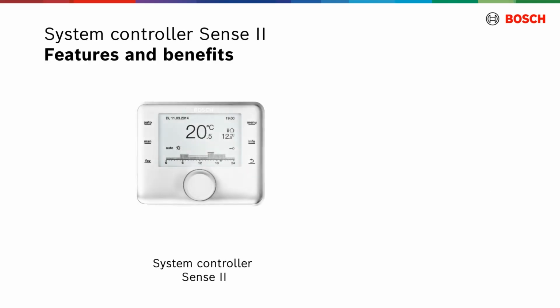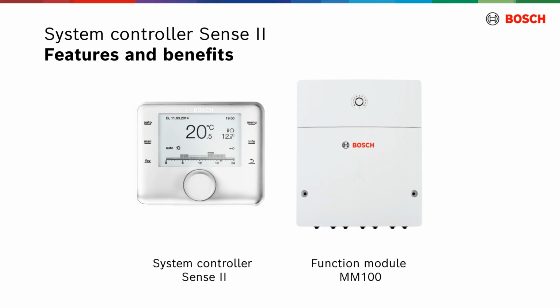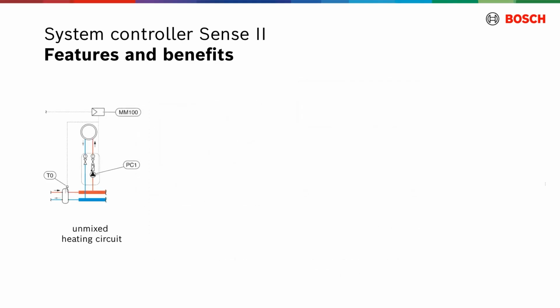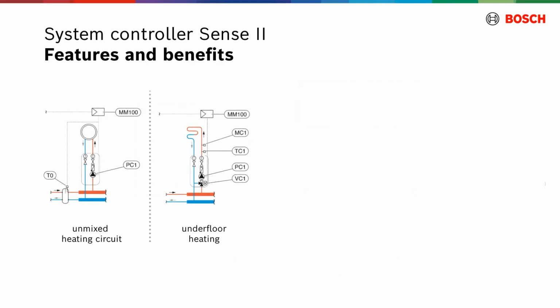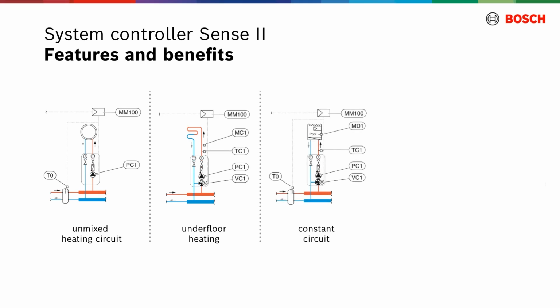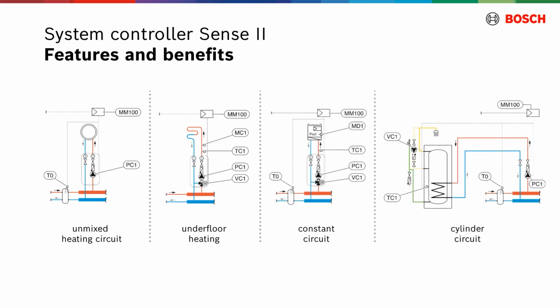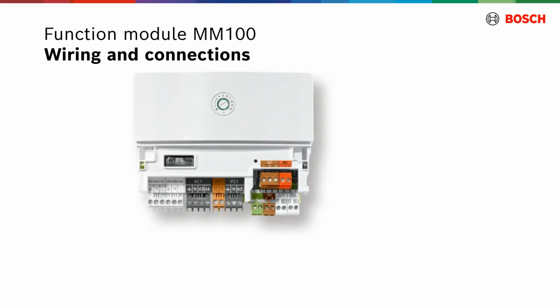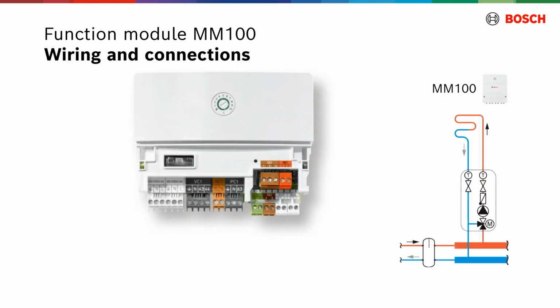Weather compensation controller Sense2 is designed to provide precise and efficient management of the heating system. Combined with the function module MM100, it can control up to 4 unmixed or mixed heating circuits, a heating circuit with a constant temperature, or a cylinder circuit with separate loading pump and circulation pump. Every assigned heating or cylinder circuit requires function module MM100. Function module MM100 serves one assigned circuit.